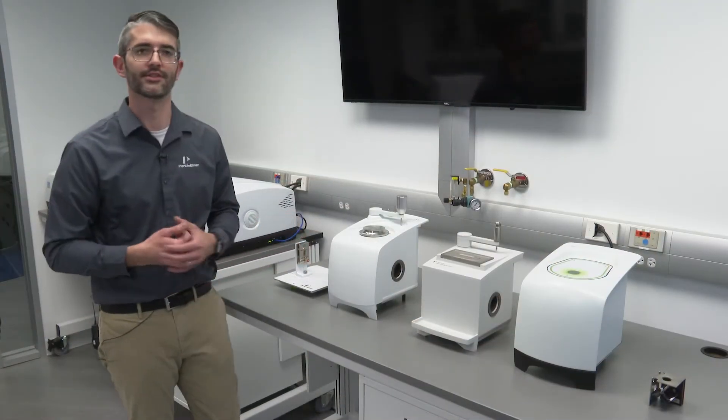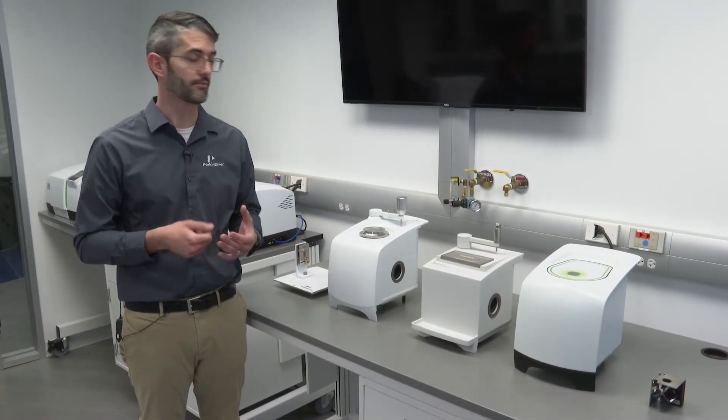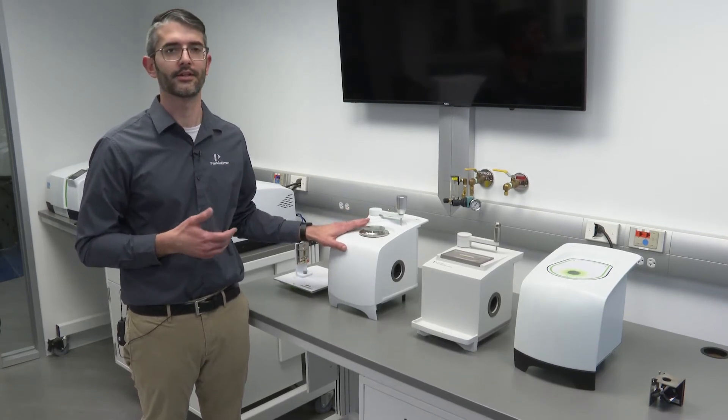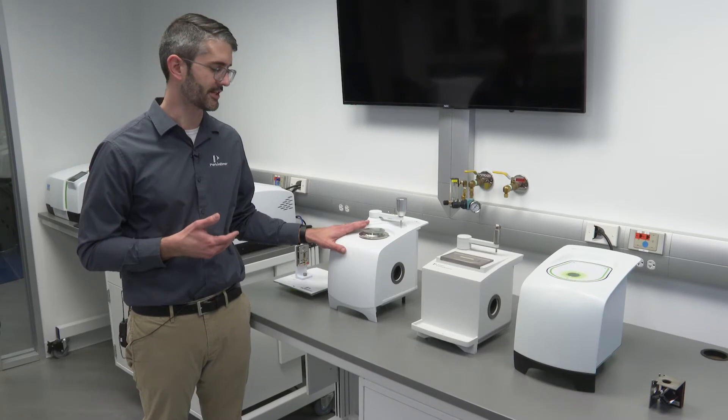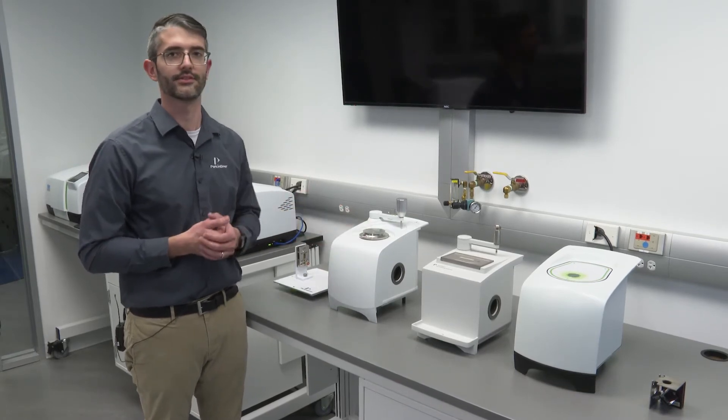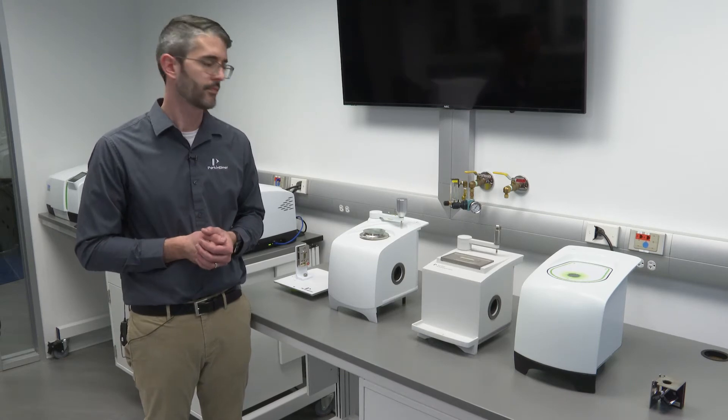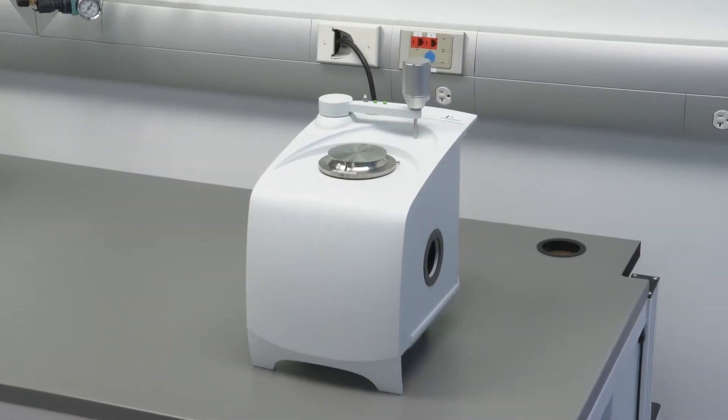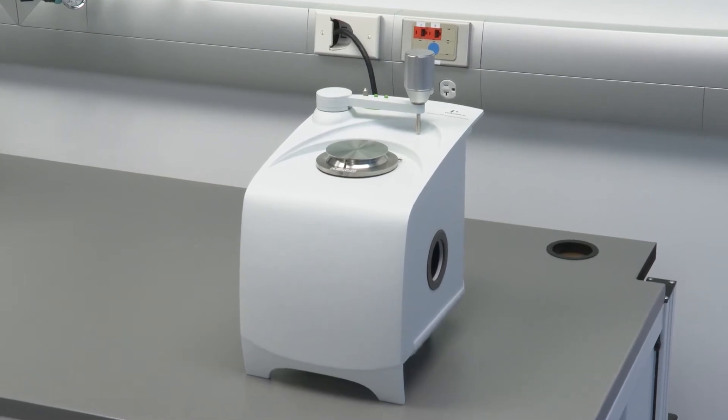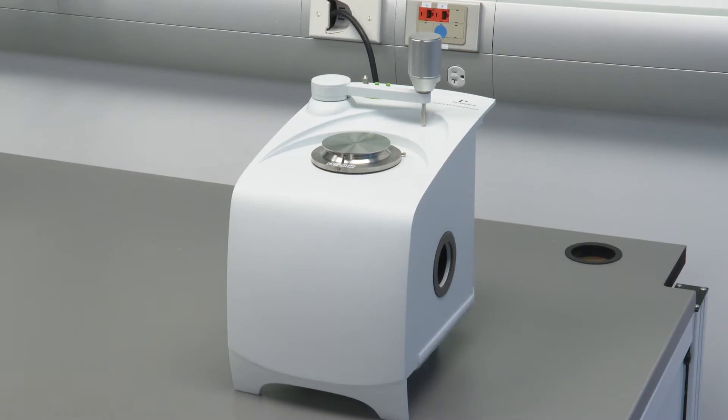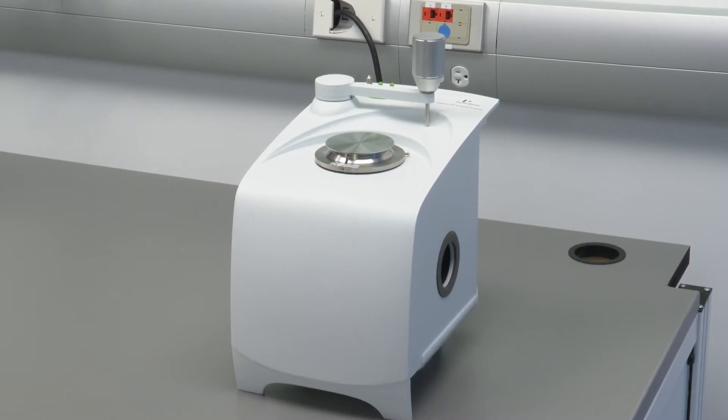Typically, when working with solid materials, as well as some liquid materials, the ATR sampling technique is employed. ATR stands for attenuated total reflectance, and a wide variety of crystal materials are available for these sampling accessories. Here we see a one-reflection ATR. This is a good all-purpose crystal format for a wide range of materials. It's extremely rugged, and it's very easy and quick to get a very high-quality spectrum of a wide range of materials.